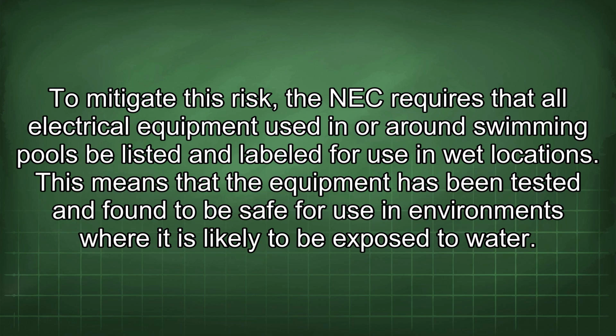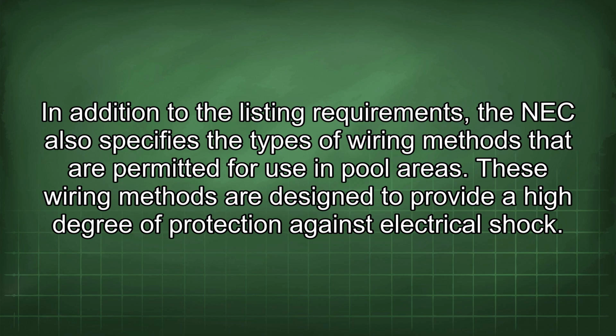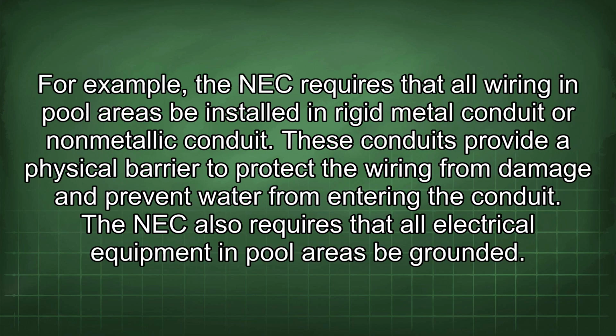This means that the equipment has been tested and found to be safe for use in environments where it is likely to be exposed to water. In addition to the listing requirements, the NEC also specifies the types of wiring methods that are permitted for use in pool areas. These wiring methods are designed to provide a high degree of protection against electrical shock. For example, the NEC requires that all wiring in pool areas be installed in rigid metal conduit or non-metallic conduit. These conduits provide a physical barrier to protect the wiring from damage and prevent water from entering the conduit.